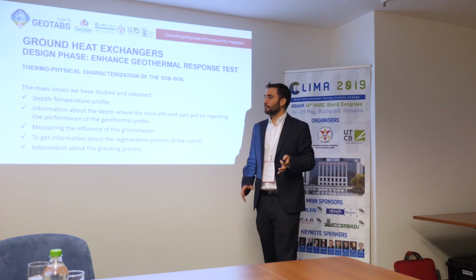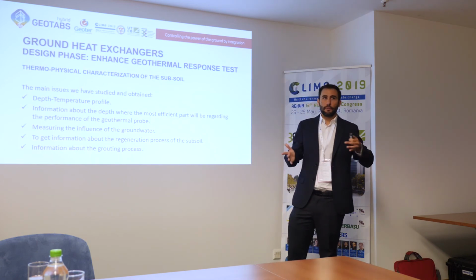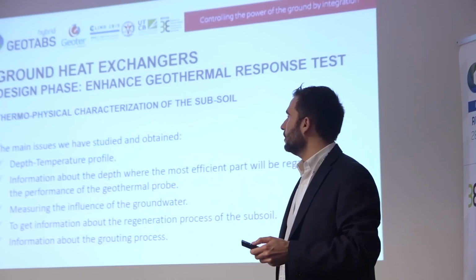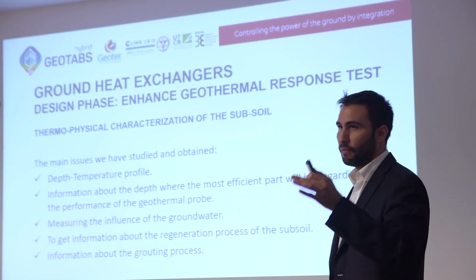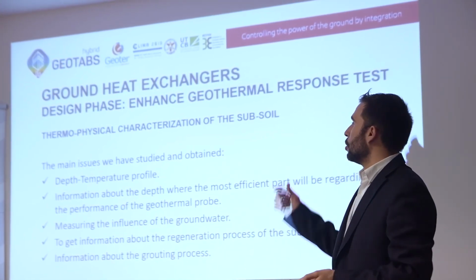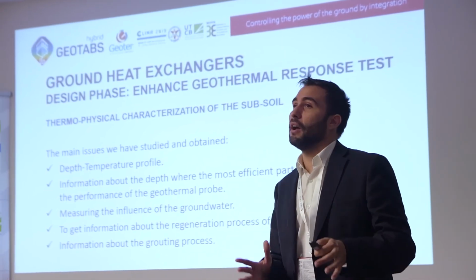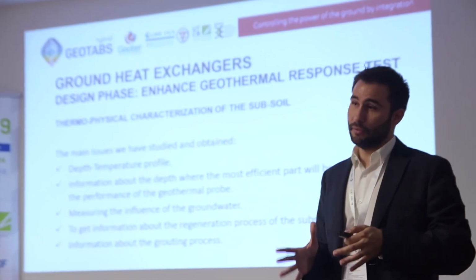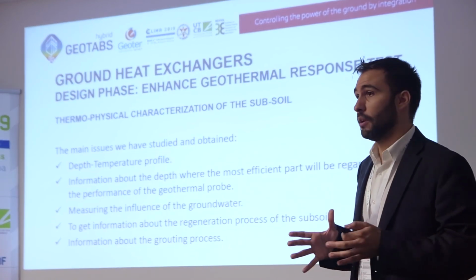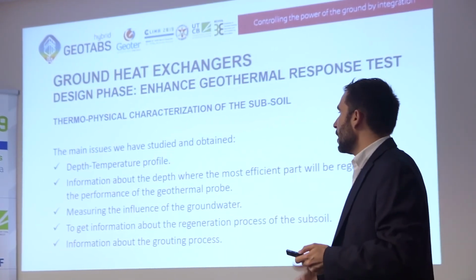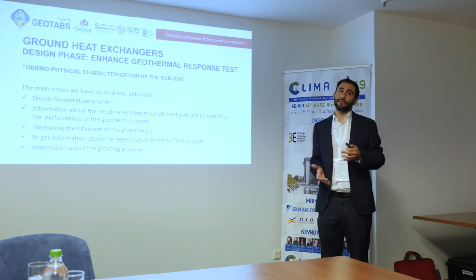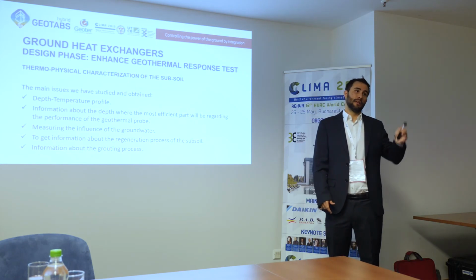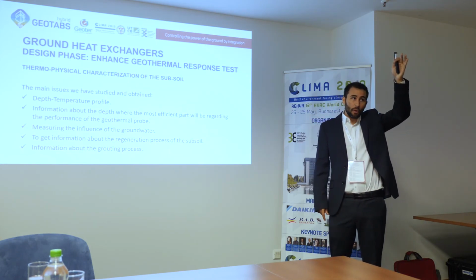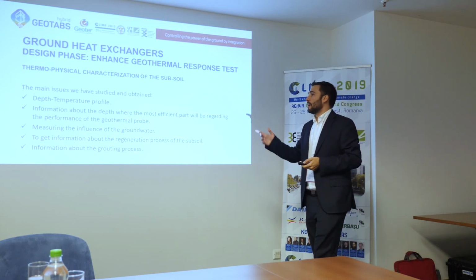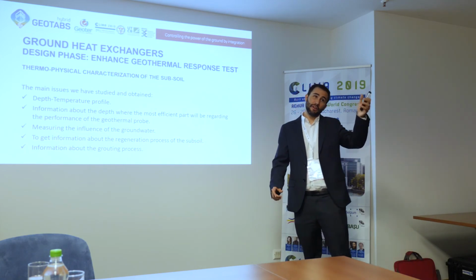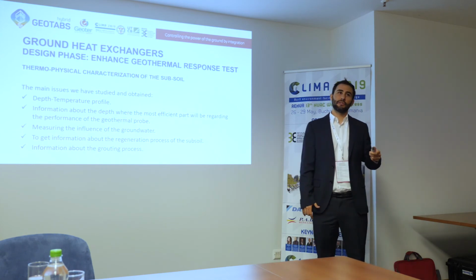This is very important because we don't obtain only average values, we obtain the depth temperature profile of the complete borehole. We have information about where the most efficient part of the geothermal probe of the borehole is. We can measure the influence of the groundwater. We can locate if we have groundwater flow at the different levels, and we can get information about the regeneration process and the grouting process too.